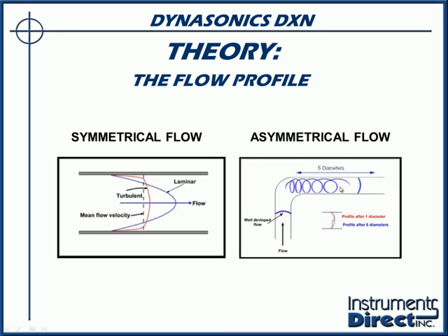The picture to the right is referred to as an asymmetrical flow profile. For example, in this case I have flow coming up the pipe. You notice the distance on the inside of this elbow is shorter and the distance on the outside of the elbow is longer, so you tend to get a tumbling effect after this elbow. If you were to put your transit time flow meter right here, it probably would just error out and you wouldn't get any data at all. So what you need to do is go downstream your 10 to 15 pipe diameters and put your flow meter there for optimum performance.